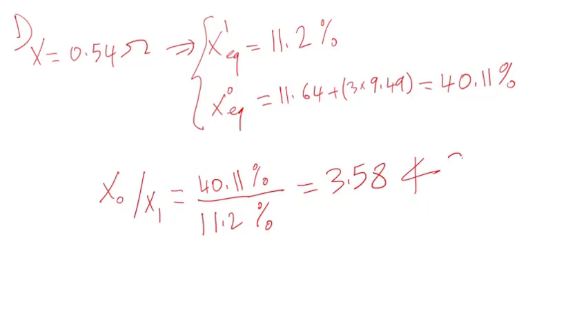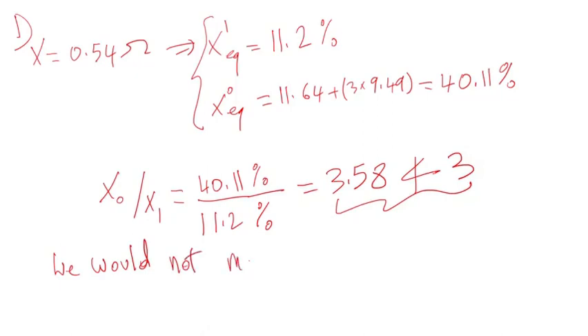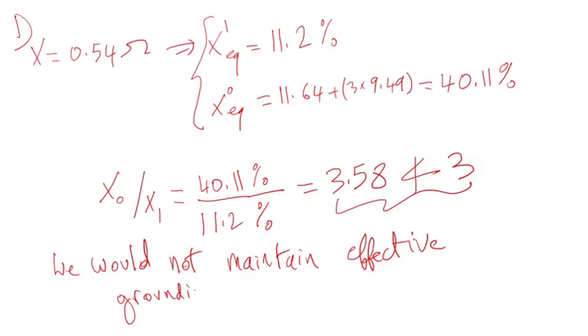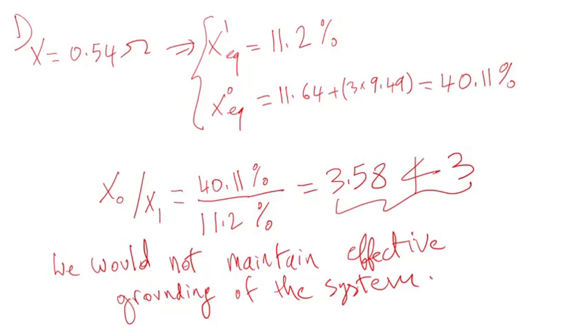The ratio calculates to be 3.58, which is not less than three. So with this neutral grounded reactor, we would not maintain effective grounding of the system. Therefore, we don't need to check the second condition — the ratio of the zero sequence resistance to the positive sequence reactance.